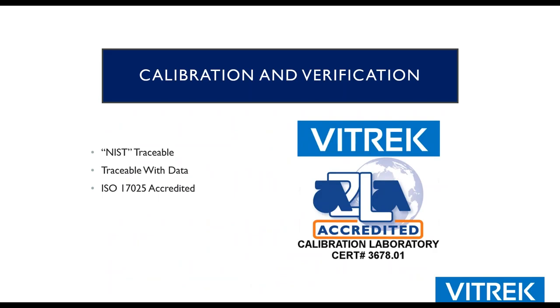As Don mentioned earlier, we are an ISO 17025 accredited facility. We're accredited by A2LA. Your own quality standards are ultimately going to dictate what you need for calibration. At minimum, everyone needs a 1 or 2 year NIST traceable calibration interval, but we also do offer these cals. The greatest thing about it is you can order a product and it's going to come immediately with an accredited cal if you choose to, and you can start using it that day.